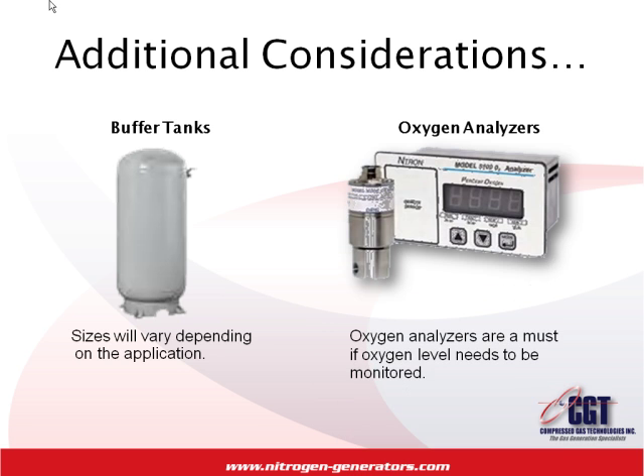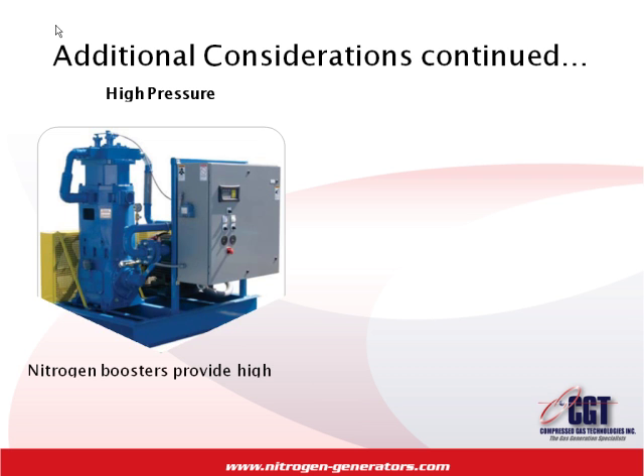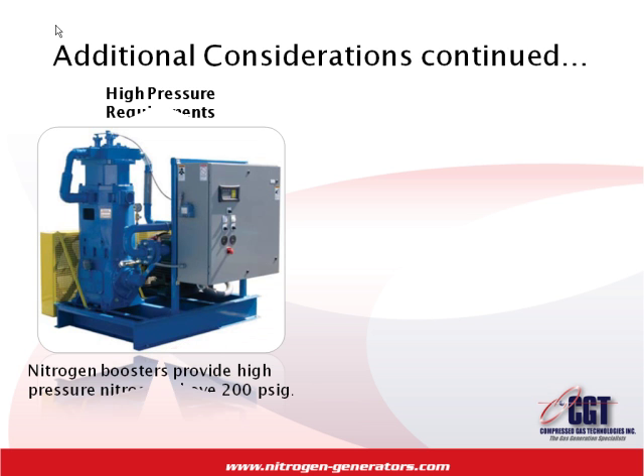Some applications are very critical and the oxygen levels need to be monitored. Oxygen analyzers are a must in this instance. Customers that need high pressure nitrogen, typically above 200 PSIG, will require a nitrogen booster to elevate the nitrogen pressure to the required level.